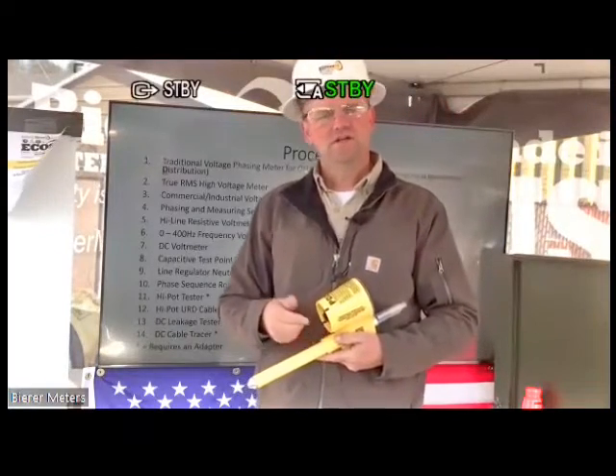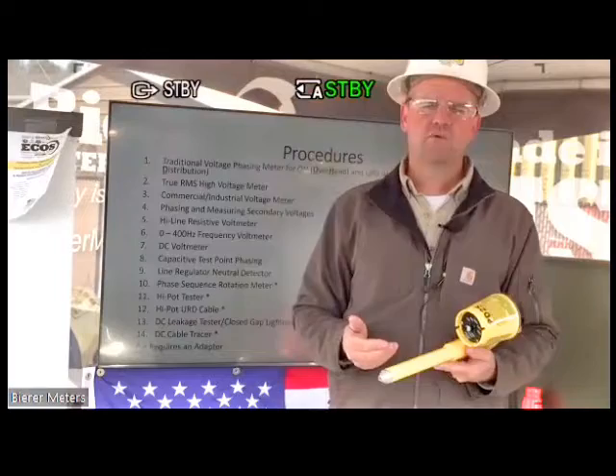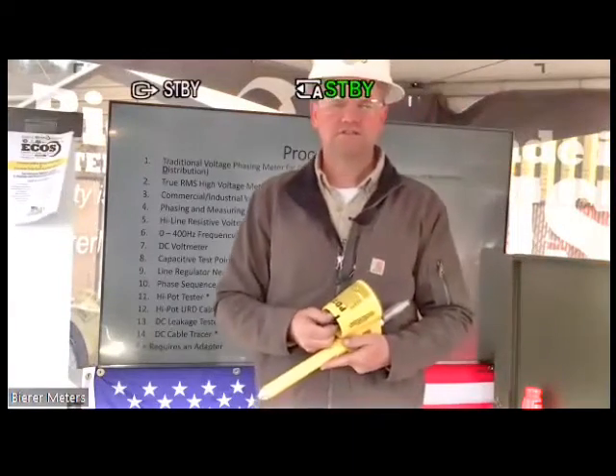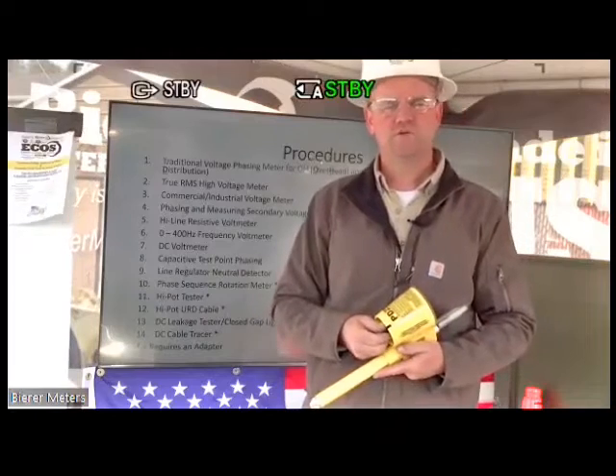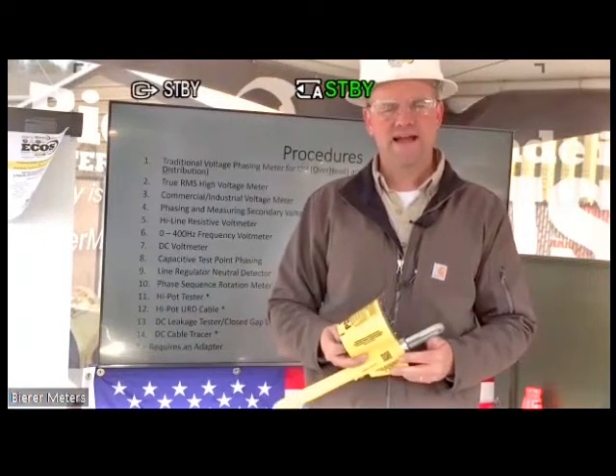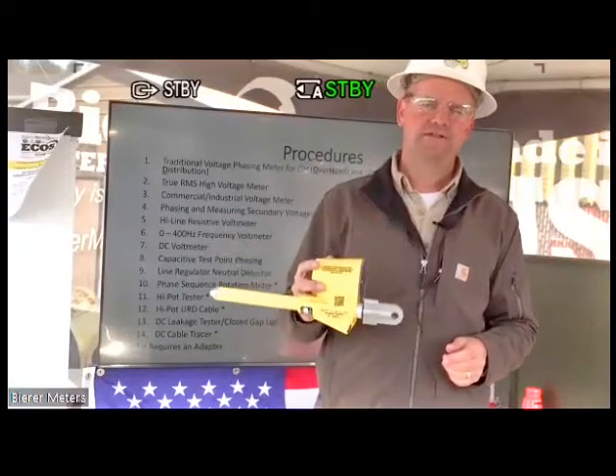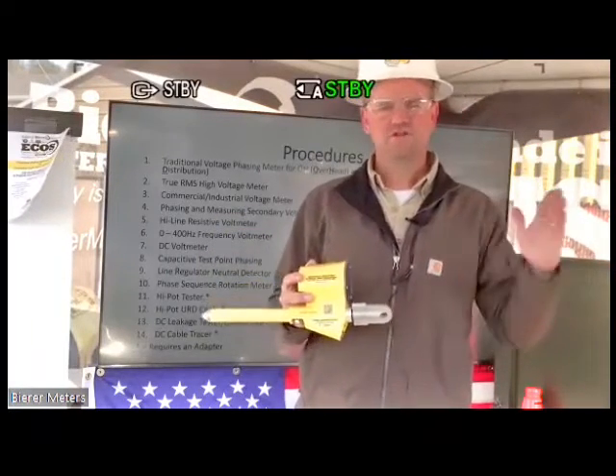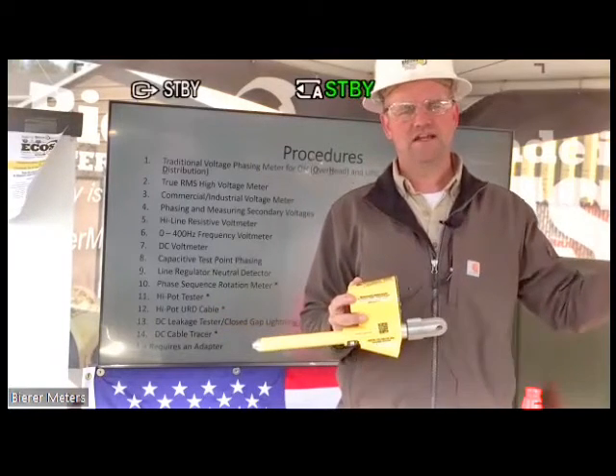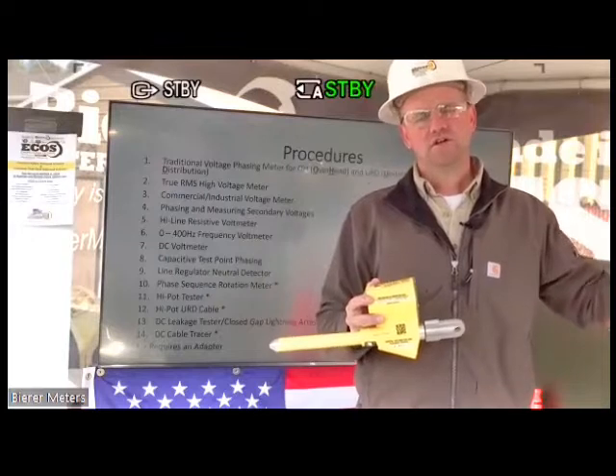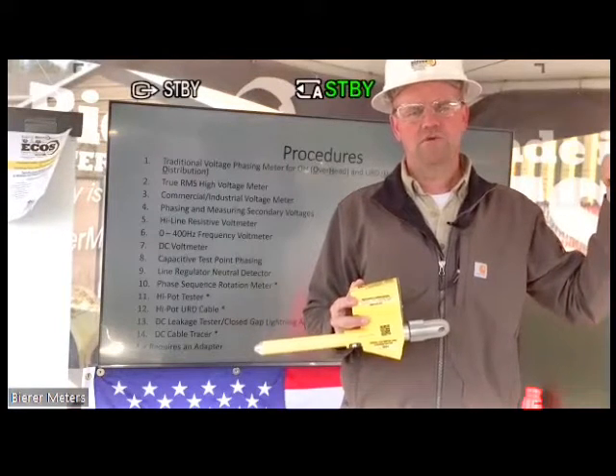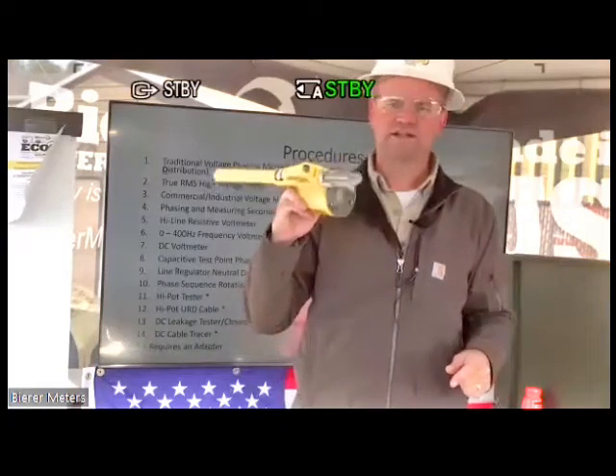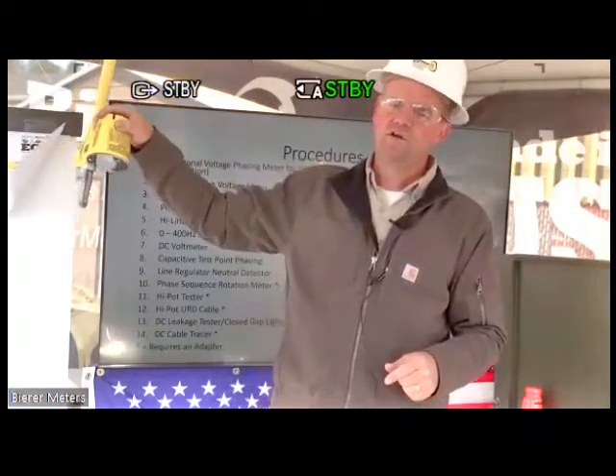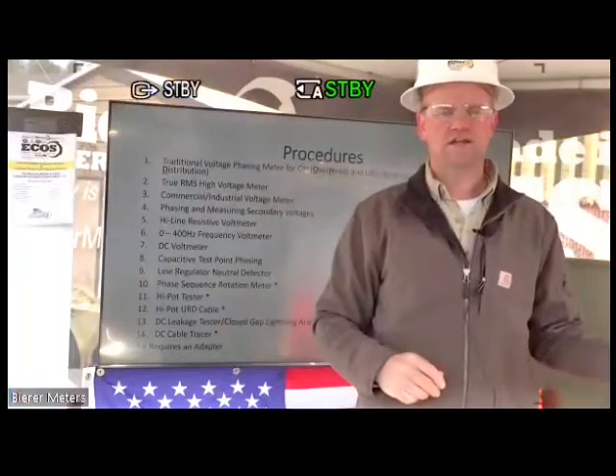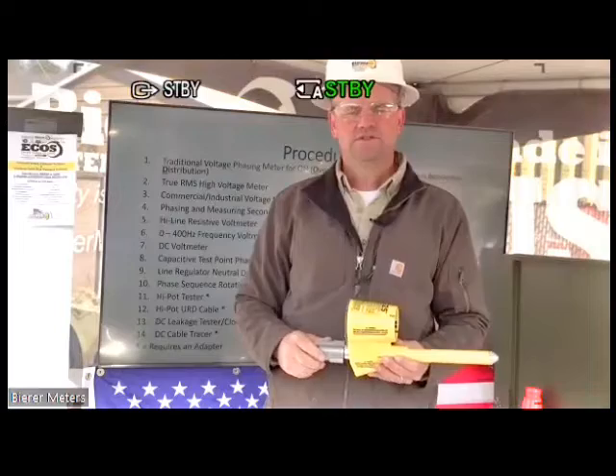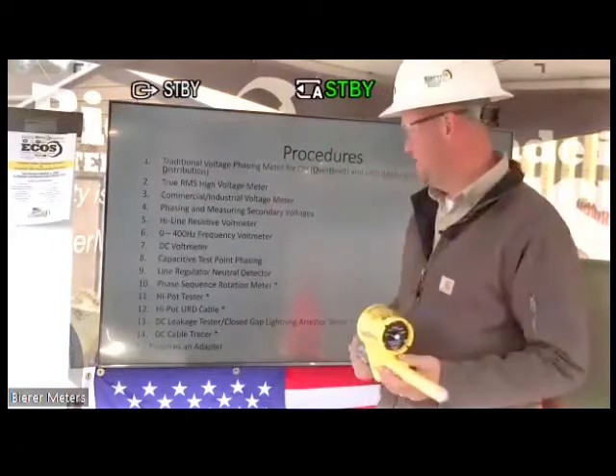A phase rotation meter, a lot of times, tells you if it's clockwise or counterclockwise, and we'll demonstrate in just a few minutes how this tool can be used as a phase sequence meter. An extremely nice feature is that I can do that on primary. Normally you have to ride the line and find a three-phase secondary tap to determine the sequence, and then correlate that with your primary. Here I don't have to ride the line, I can determine my sequence on the primary. Or if you want to do it on secondaries, you can, just like you utilize your tool now. So again, extremely useful, saves a lot of time.